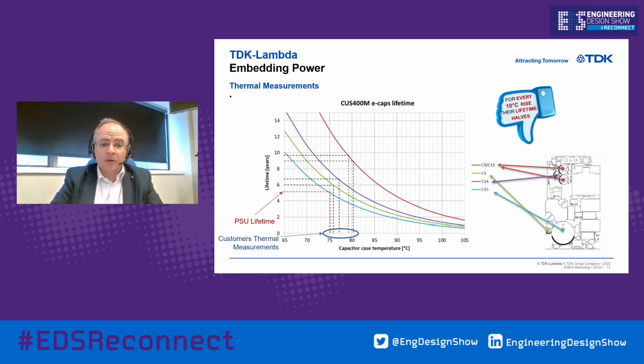If you can ensure cooling of the power supply to reduce the C15 to, say, 65 degrees C, then your lifetime would double to a minimum of 10 years. Of course, this is assuming continuous operation. If the power supply is only operational for, say, 6 hours a day, then your actual lifetime estimate can be quadrupled.